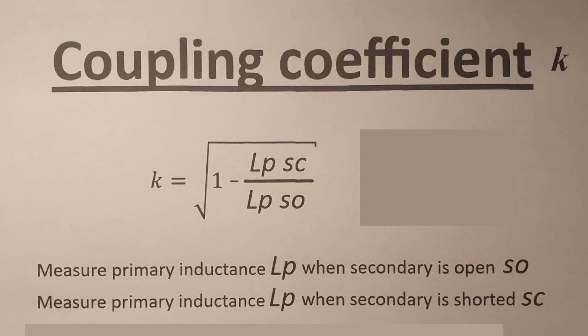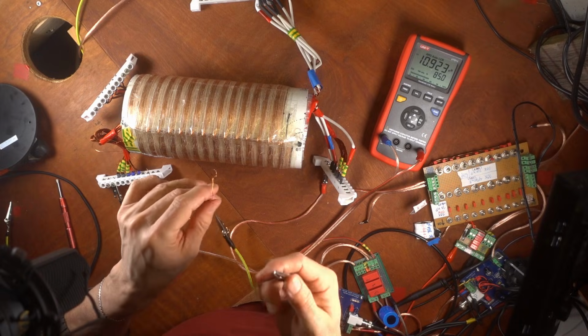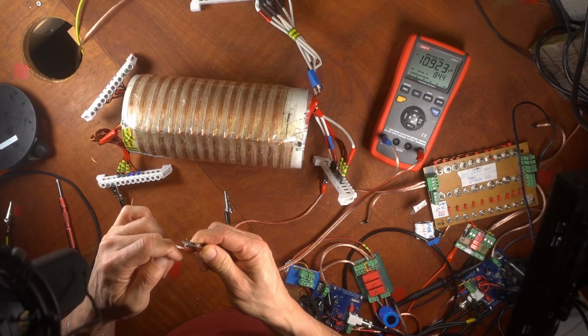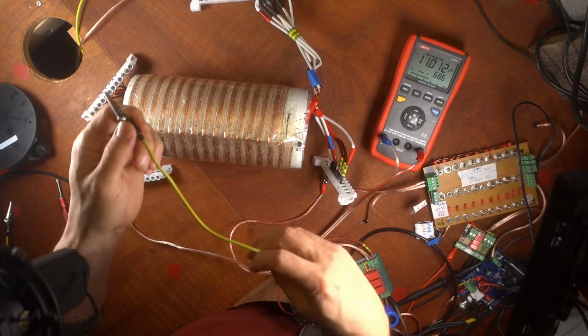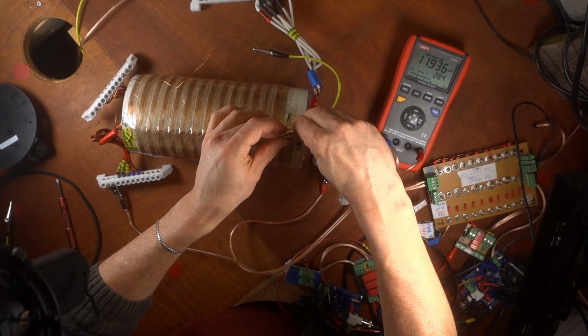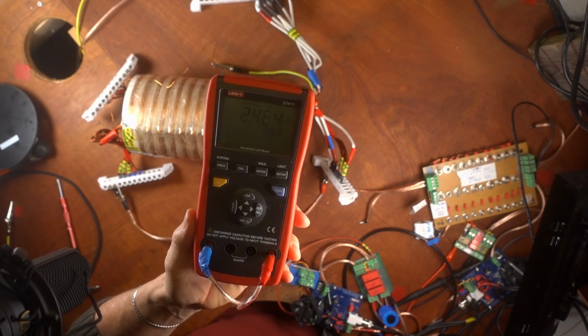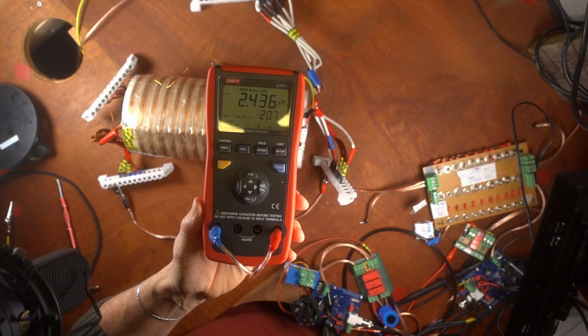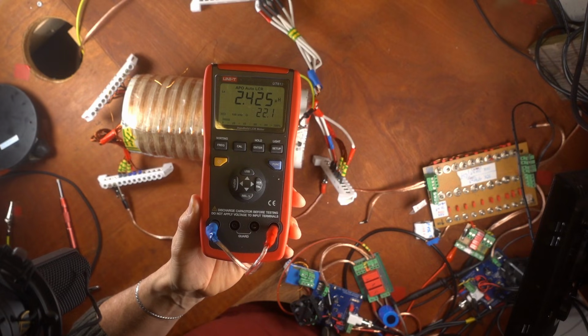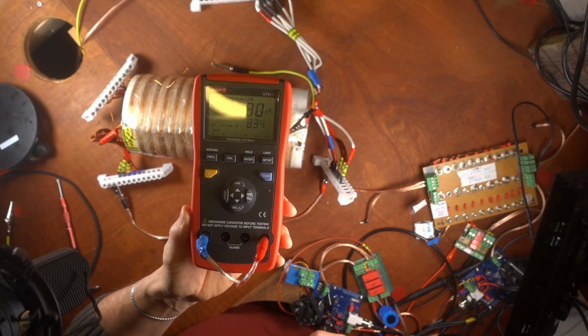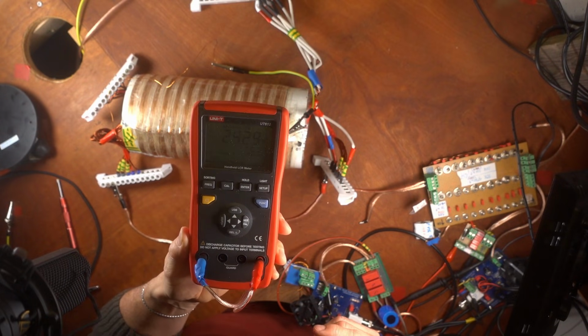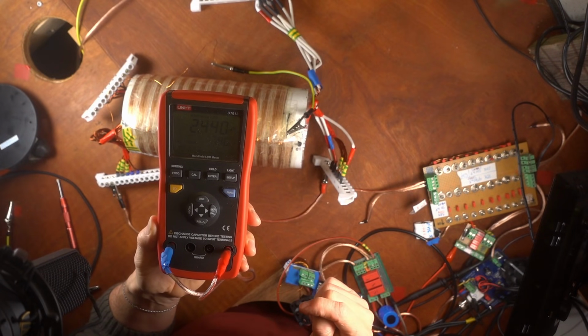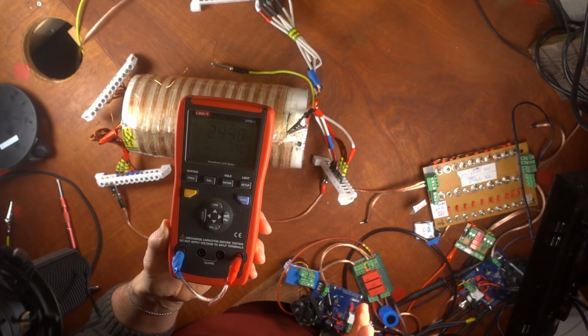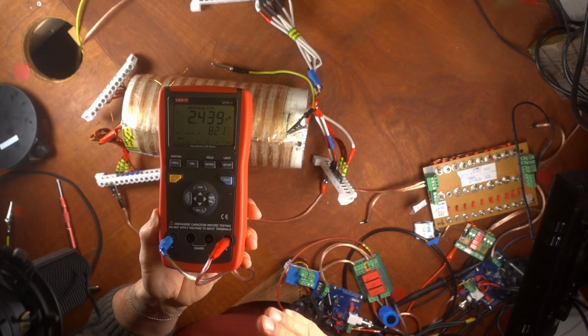Let's first do something else. We are measuring still the high current coil. So now I will short out the high voltage coil and see what the coupling factor is there. So I'm still measuring the current coil inductance, and now I've shorted out the high voltage coil. And as you can see, it now measures 2.426 microhenries. This means there's still a strong coupling factor between the current coil and the high voltage coil on the outside, but it is a little bit less because the inductance is a little bit higher.